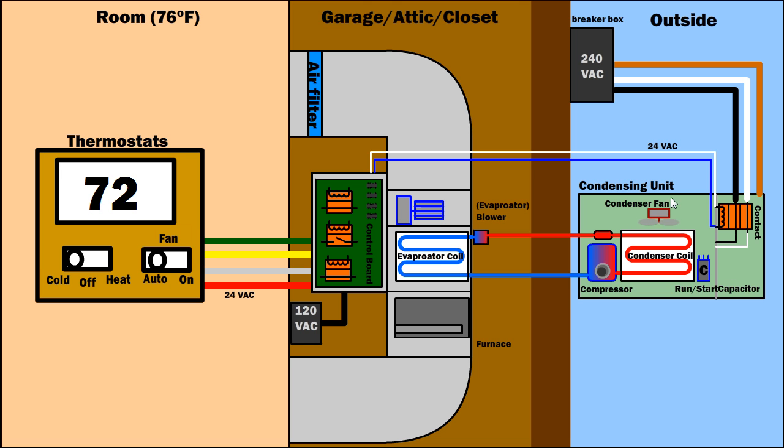So it kicks on the run and start capacitor, then if you don't see the fan come on, then if you're sure that the capacitor is working but the fan doesn't come on, then you might have a bad fan. You might have loose connections in between. So that's the next thing you want to check. And then of course, if the fan comes on but you don't hear this humming sound from the compressor, then you know that the compressor isn't working. So you should hear three sounds. You should hear the vibration from the contactor, you should hear the humming sound from the compressor, and you should see the fan blowing air. So there's three sounds, wind blowing sound, compressor, and a contactor. If you don't hear all three sounds, then something is wrong.